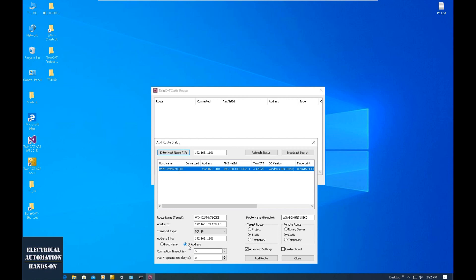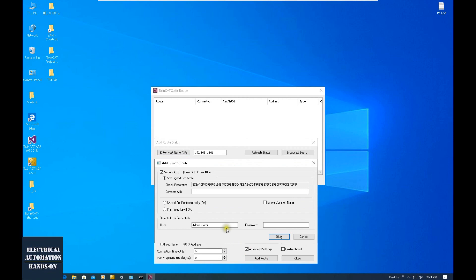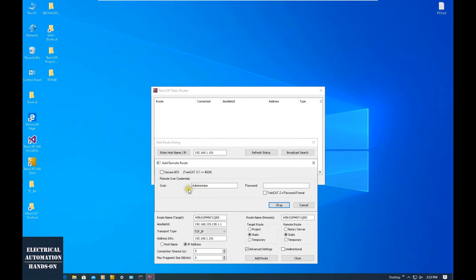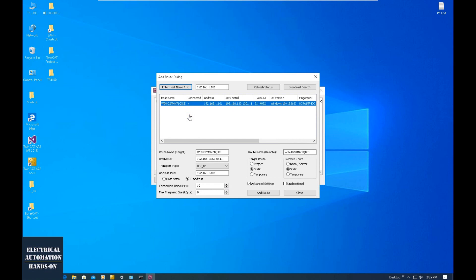Let's hit the IP address and make sure that it is static. Check the advanced settings. If you are remotely communicating with this controller, probably the connection timeout should be set to 10 seconds, because sometimes if we try to use a VPN or remote connection to a PLC, that timeout should be larger — for example, 5 to 10 seconds or even higher. After this, let's hit 'Add Route', uncheck 'Secure ADS', and the default name is administrator. Password is 1 — that is the default username and password from the Beckhoff controller. Once we get a connection, the connected status will show a cross, meaning the second laptop already found the online controller. Hit close.